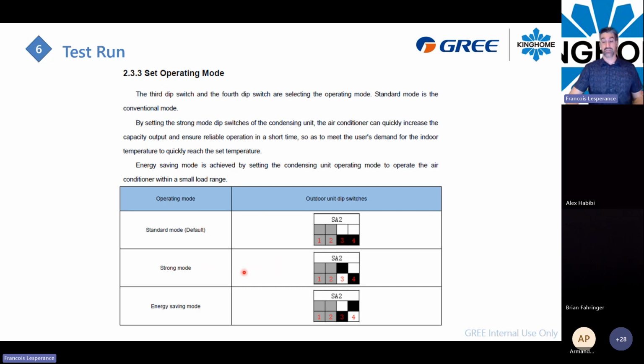The reverse can be done too. Even if you have installed a 3-ton unit cabinet, and a 2-ton would be lower, you can reduce the capacity by enabling the energy saving mode. You will just have to flip those dip switches: number 3 off, number 4 on, and you will enable the energy saving. The compressor will take a little bit longer to operate the algorithm and all of that, so it will reduce the capacity a little bit, and the system can act like a 2-ton and a half.